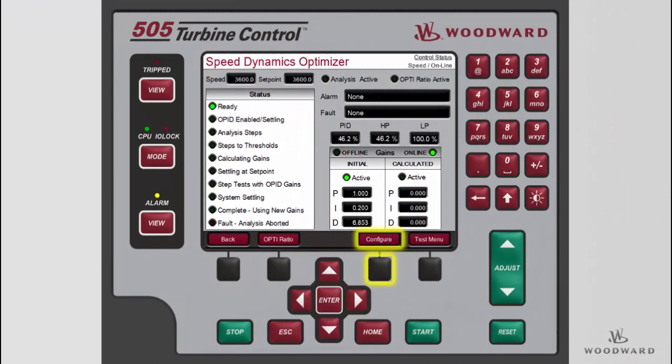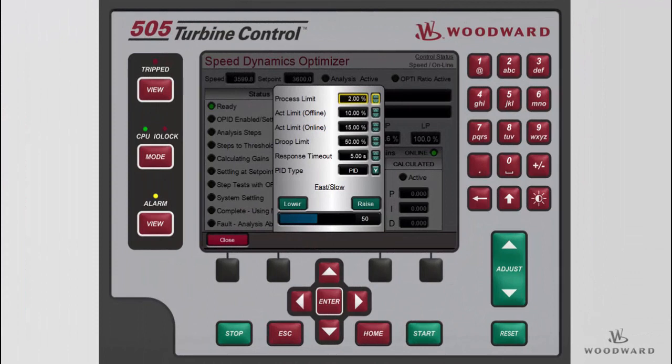To configure the test, press the Configure Softkey to launch the pop-up menu. The default values should work for most systems without needing adjustments. However, we will cover each of these settings so that the test can be modified to meet the needs of your system. The process limit is the amount of movement allowed in the process signal during the test. If movement occurs during automatic tuning that exceeds this value, the automated test routine will abort and control at the initial setpoint. The limit is centered around the current process value at the time the test is enabled. For example, if the process limit is 2% and the speed signal is at 3600 RPM, then the upper movement limit is 3600 plus 2% of 3600, which equals 3672 RPM.